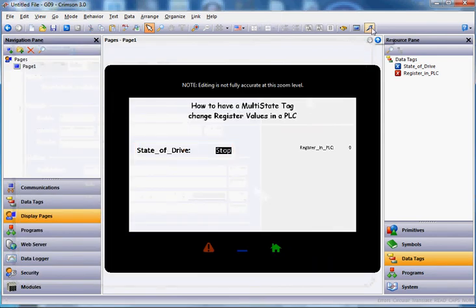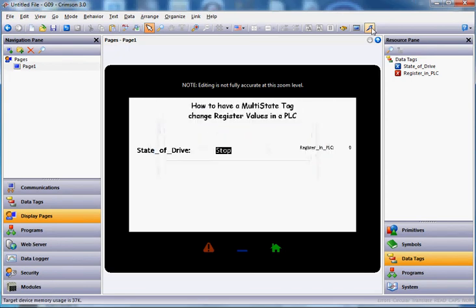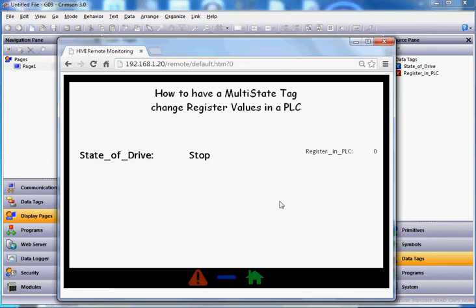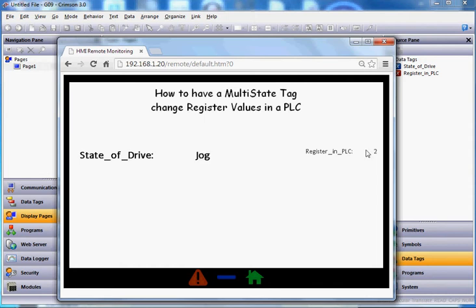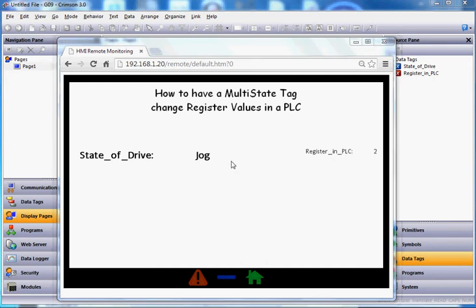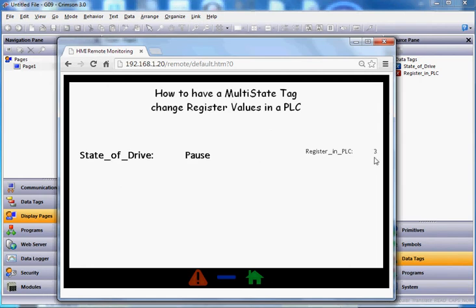So according to the logic now, whenever we change the state and hit enter, it should change the register in the PLC. I'll click OK and go ahead and download this to the HMI. I'll go back to the web browser — notice the register in the PLC is currently at zero. If I hit stop and then select jog and hit enter, look — it changed to number two. If I click again, change to pause and hit enter, it says number three. That works pretty well — exactly what we were looking to have done.